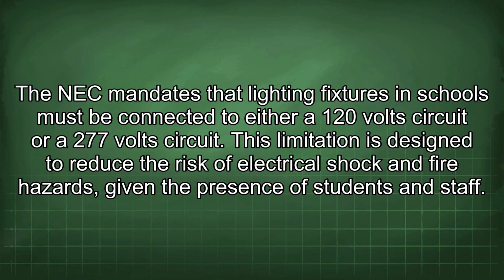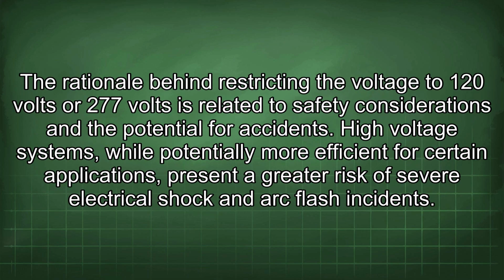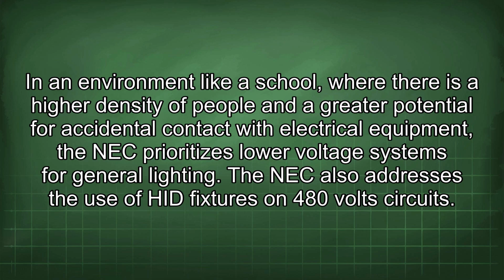This limitation is designed to reduce the risk of electrical shock and fire hazards, given the presence of students and staff. The rationale behind restricting the voltage to 120 volts or 277 volts is related to safety considerations and the potential for accidents. High-voltage systems, while potentially more efficient for certain applications, present a greater risk of severe electrical shock and arc flash incidents. In an environment like a school, where there is a higher density of people and a greater potential for accidental contact with electrical equipment, the NEC prioritizes low-voltage systems for general lighting.